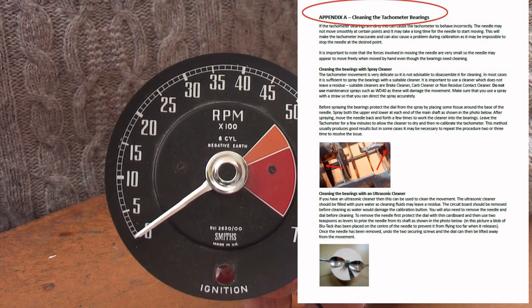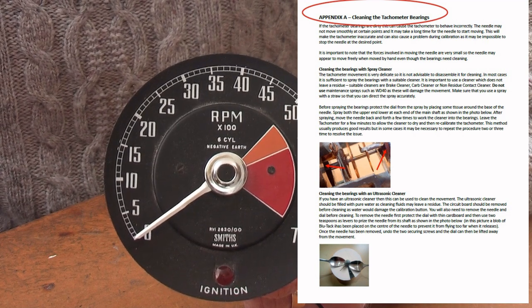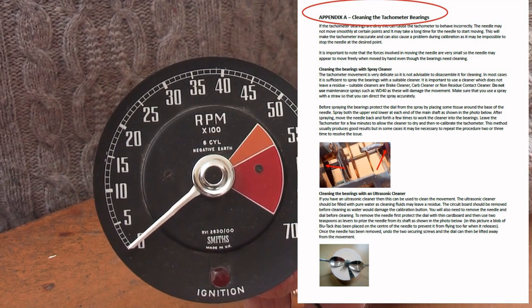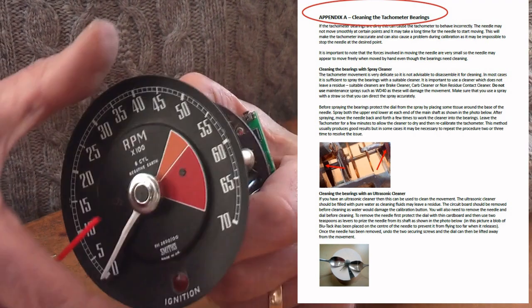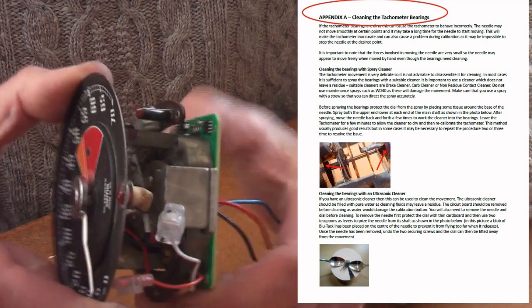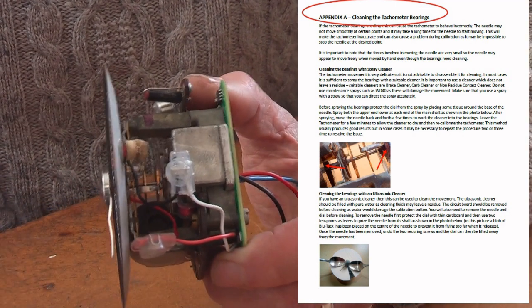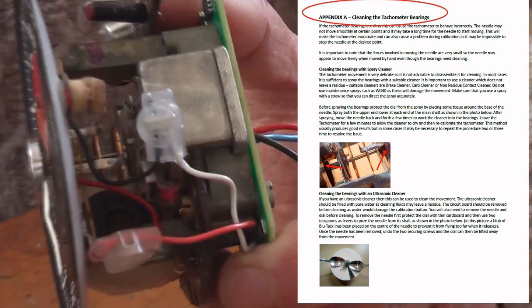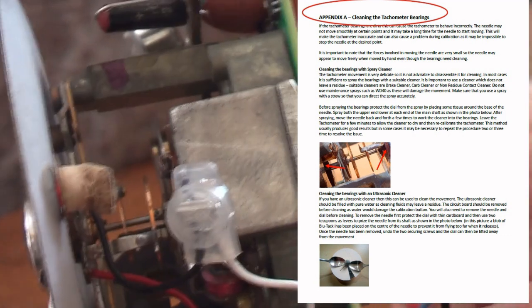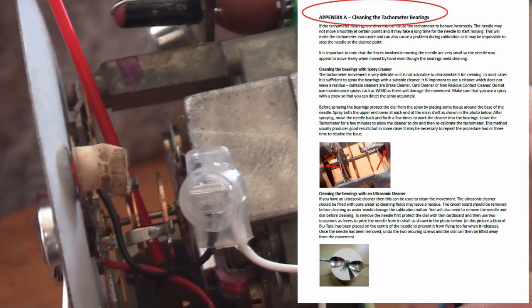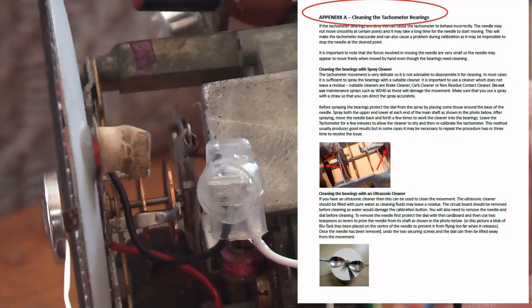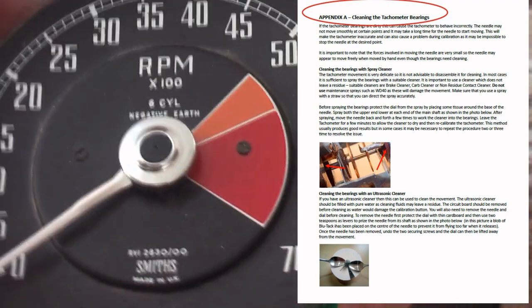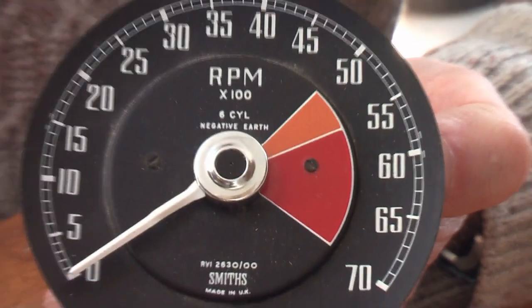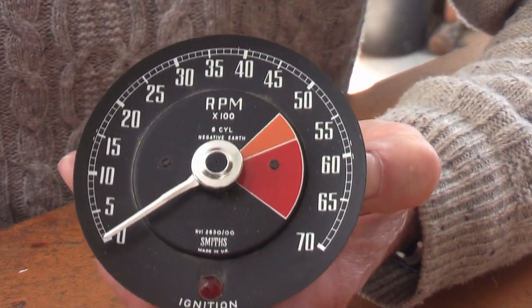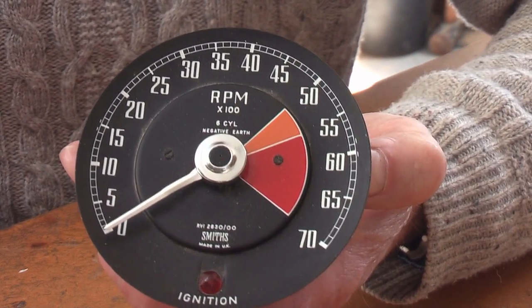Don't be tempted to use a maintenance spray like WD-40, because that will cause a lot more problems. You need to use a cleaner that has a straw on the can, and you need to clean at both ends of the shaft that moves the needle. If I zoom in here, you can see the shaft just down in there, and you need to spray at both ends of that. Once sprayed, work the needle backwards and forwards a few times, let the cleaner dry, then recalibrate. You may need to try this procedure two or three times, but it's usually very effective.